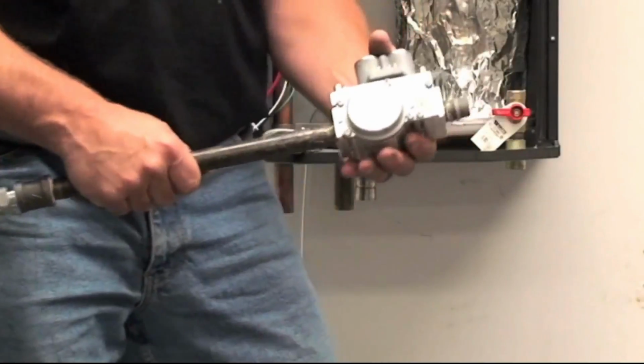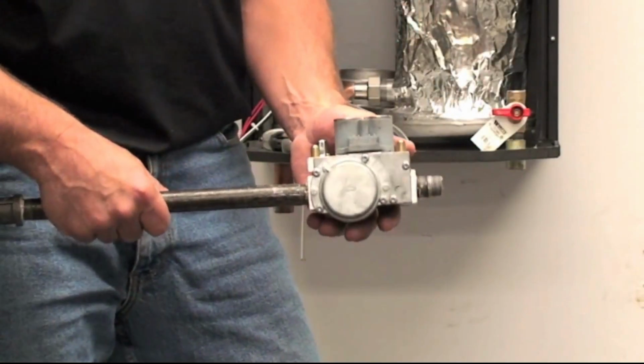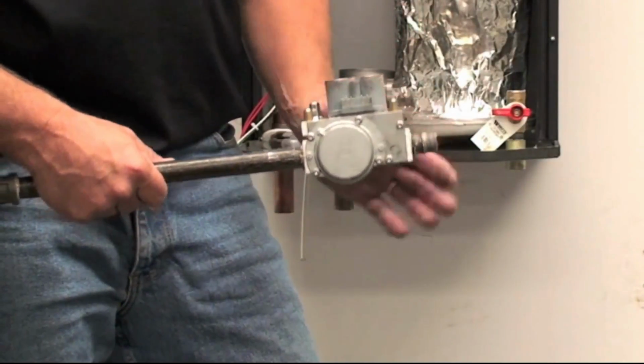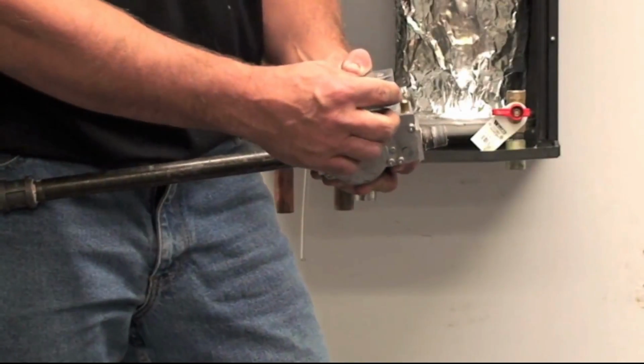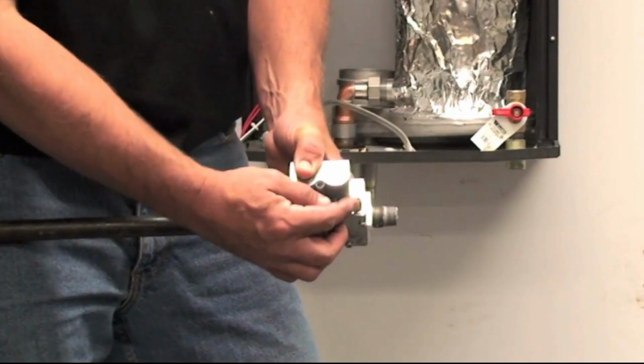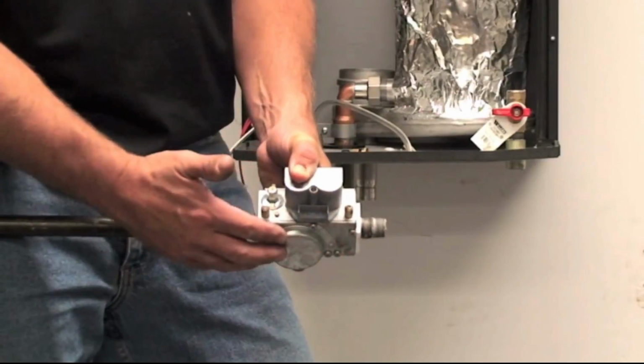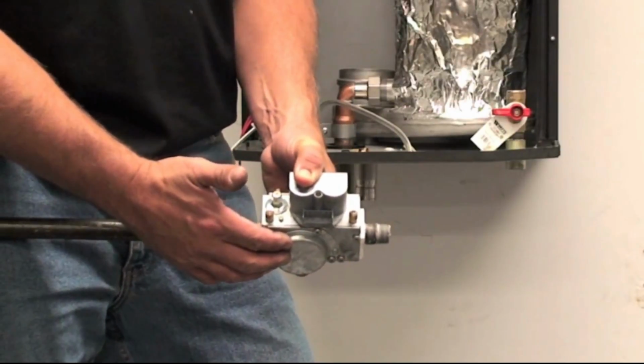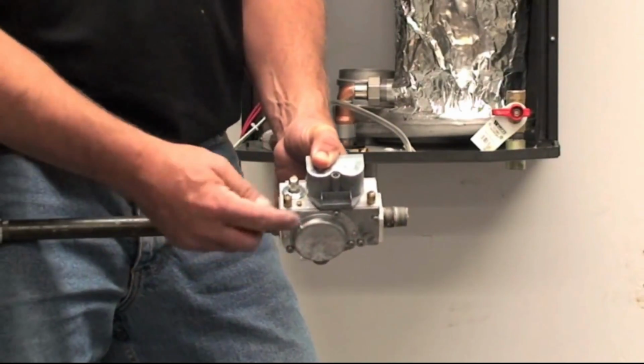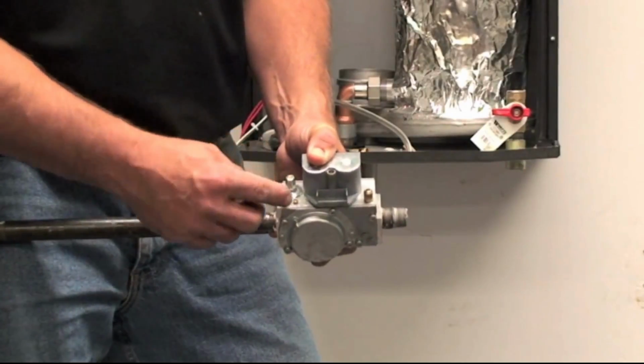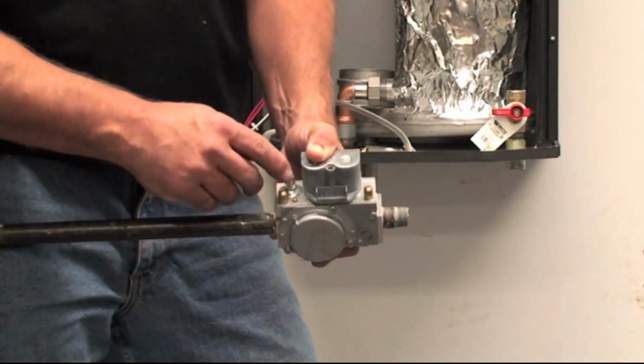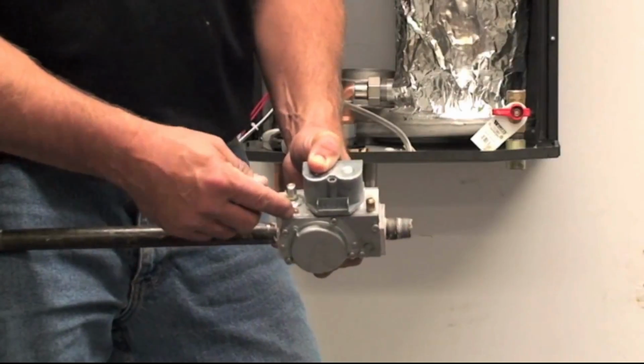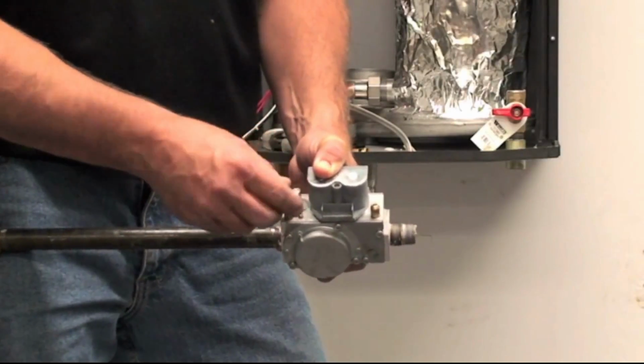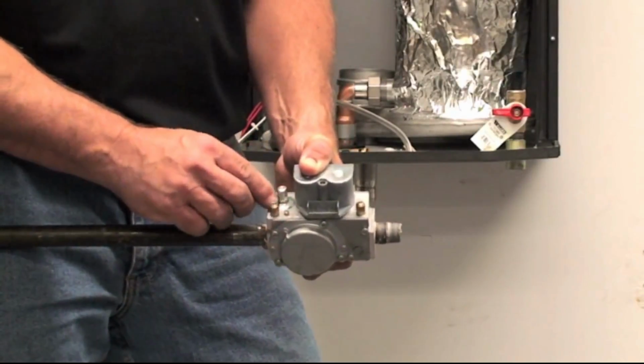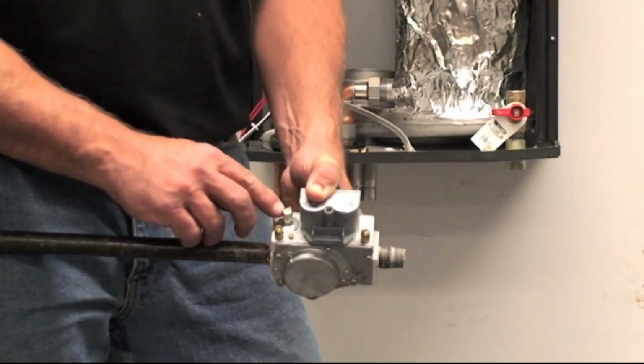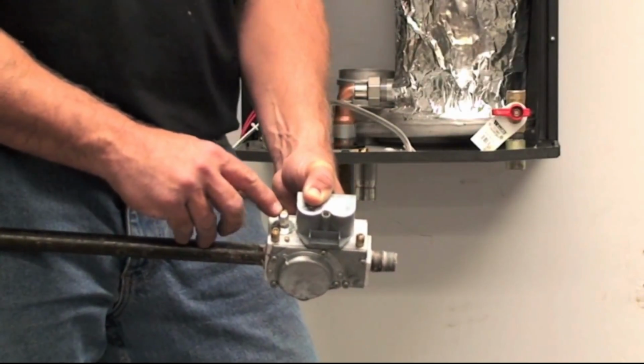This is our standard GB055 Dungs gas valve. Your solenoids are here. Your inlet gas pressure tapping is right here. It's a needle valve, so you can take pressures if you need to monitor incoming pressure. For gas adjustment into the valve, you have a throttle screw. You'll notice that there's a plus and a minus. You just rotate that either way to either increase fuel or decrease fuel. There's also this little tower here, which is your offset adjustment.